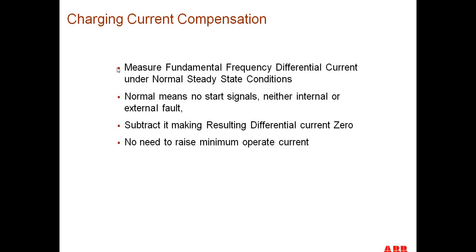So what we do is we measure the fundamental frequency of the differential current under normal steady state conditions. That means 500 milliseconds after the breaker is closed, and we have no start signals or external fault type indication. Then we subtract out that charging current from the differential current to zero it out, so we don't need to change the minimum operating level at all.